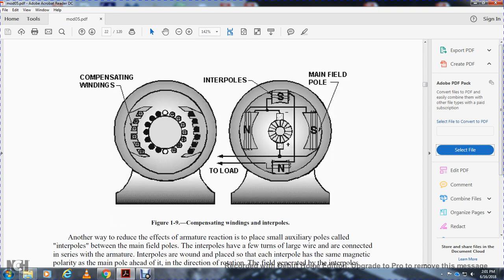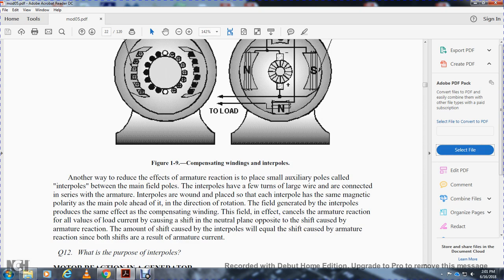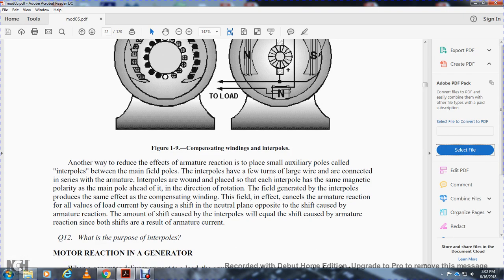As shown in figure 1-9, compensating windings and interpoles work together. Another way to reduce armature reaction is to place small auxiliary poles called interpoles between the main field poles. Interpoles have a few turns of large wire and are connected in series with the armature. They are wound so that each interpole has the same magnetic polarity as the main pole ahead of it in the direction of rotation. Interpoles produce the same effect as compensating windings — their field counteracts armature reaction for all values of load current, causing a shift of the neutral plane opposite to the shift caused by armature reaction. The two shifts cancel because both are proportional to armature current.